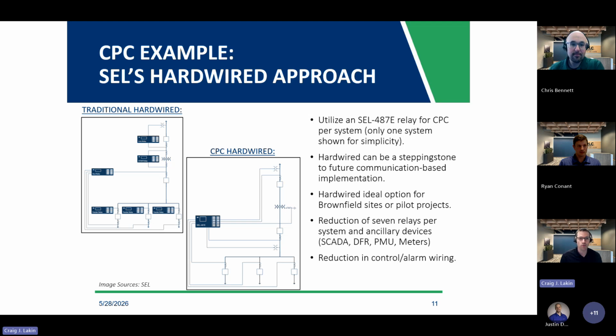That's not fully adopted by most clients or most utilities. So there would typically still be another breaker control relay for the high side breaker and another breaker control relay for the low side breaker. And those breaker control relays would be doing control, so SCADA, synchronizing, tripping. It could be doing breaker failure control if you wanted. So other functions may be built in here. So really on a typical design, you'd see about a reduction of 7 relays.